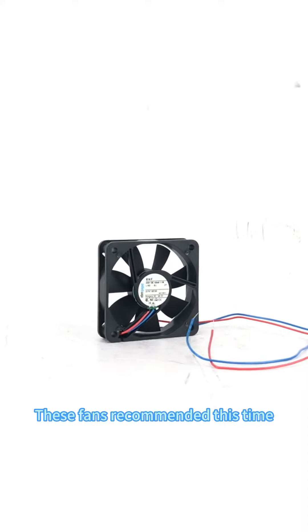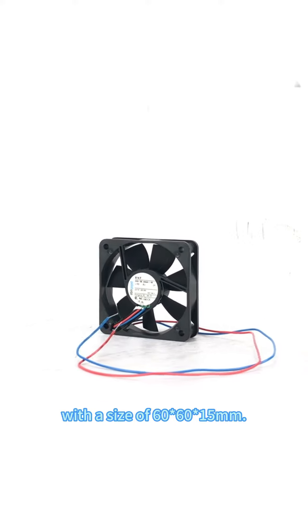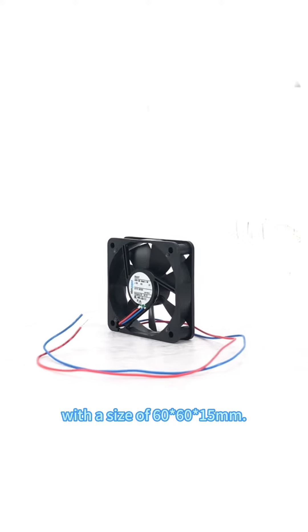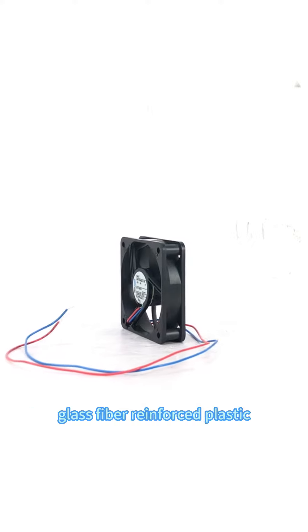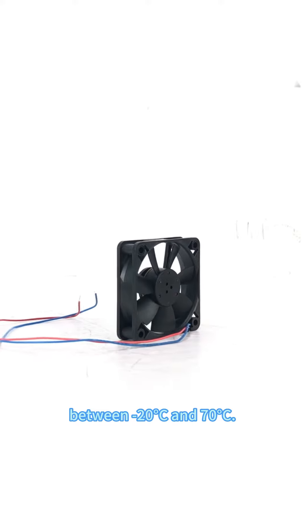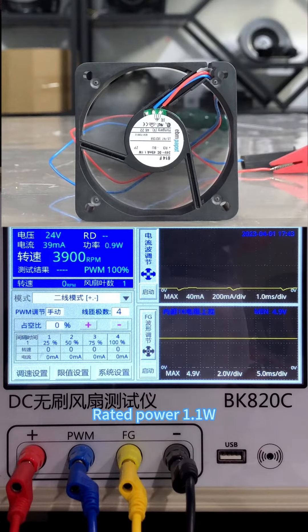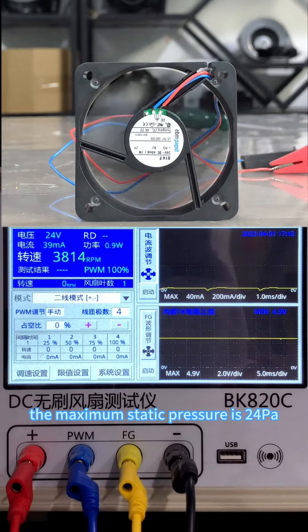These fans recommended this time are all four-wire DC fans. The first model is 614F with a size of 60 by 60 by 15 millimeters. The impeller and casing are made of glass fiber reinforced plastic, and ball bearings. The operating temperature is between minus 20 degrees and 70 degrees Celsius. Here are its parameters: rated voltage 24V, rated current 0.045A, rated power 1.1W, rated speed 3,900 RPM. The maximum air volume is 28 cubic meters per hour and the maximum static pressure is 24 Pa.